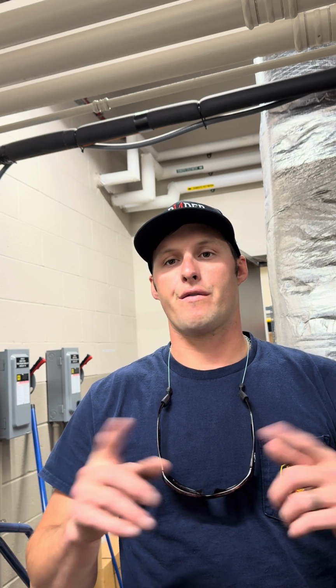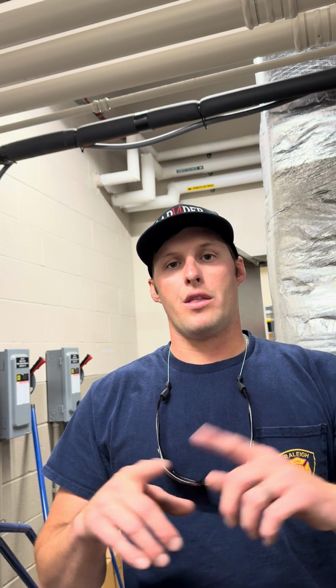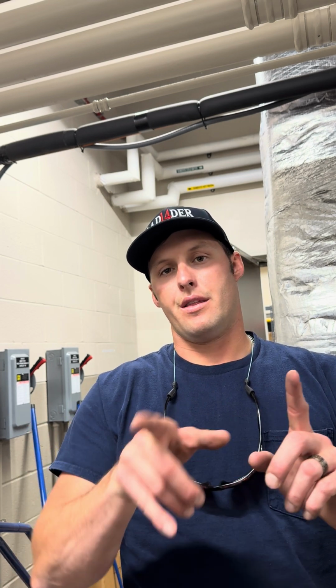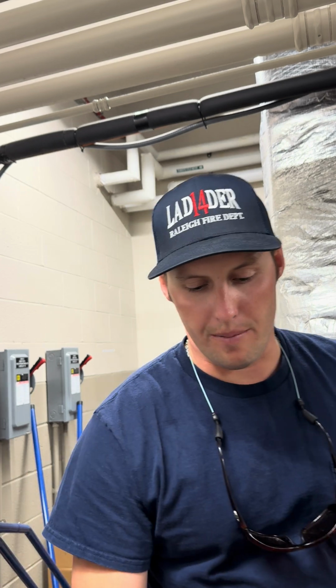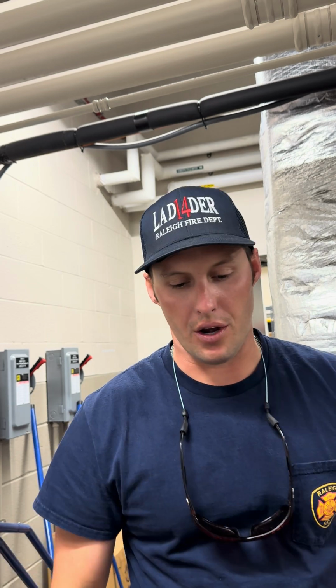Be aware of damaged wiring, insulation missing off of wiring, bad splices, and bad connections, because they could cause electrical shock, and they could cause a fire from arcing, where there's a gap and the electricity jumps that gap, and it could arc and catch something on fire. Overheating is also a concern, but other than that, electrical shock, fire potential, and HVAC systems recirculating dirty air.